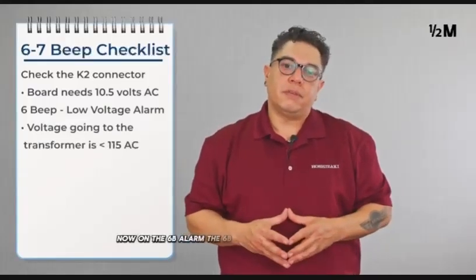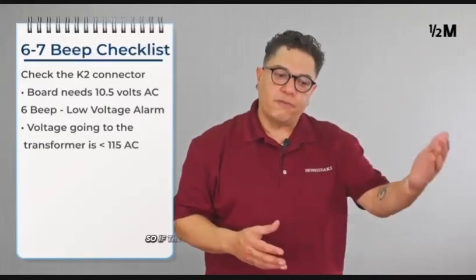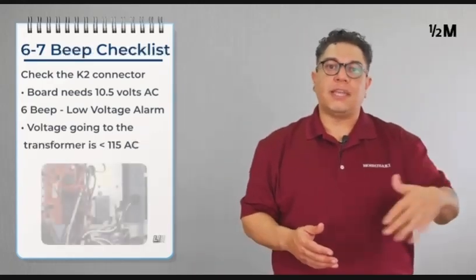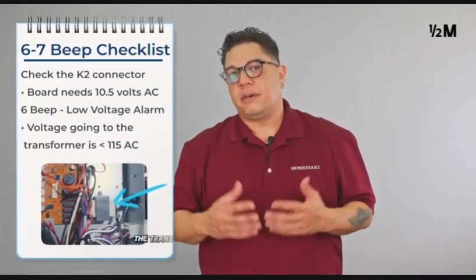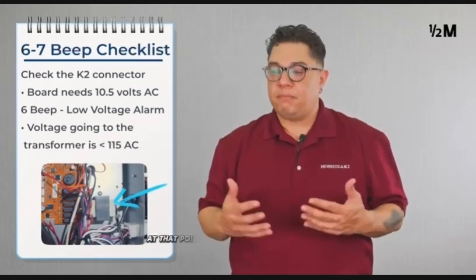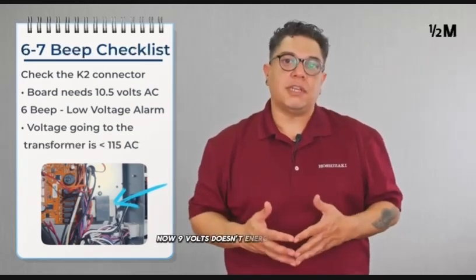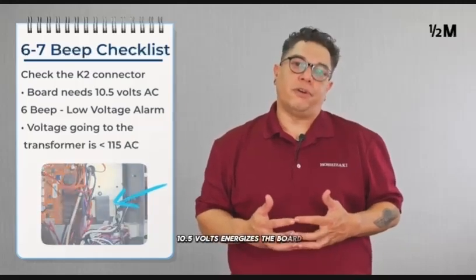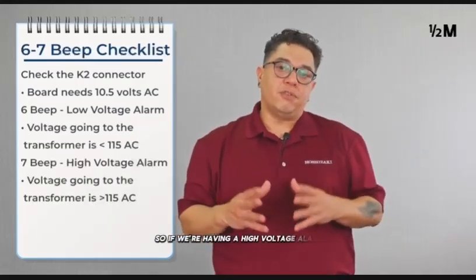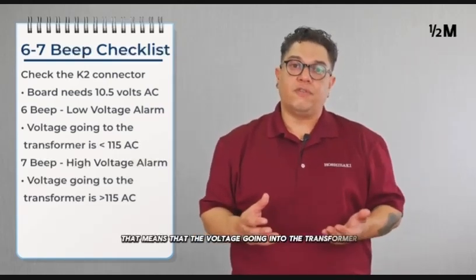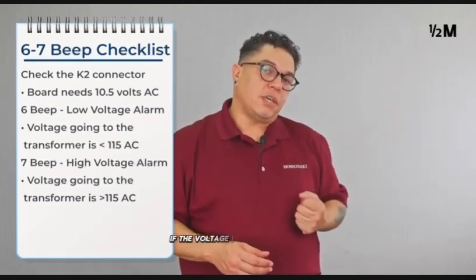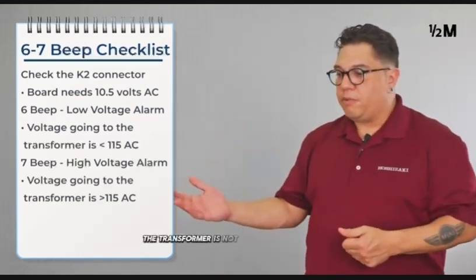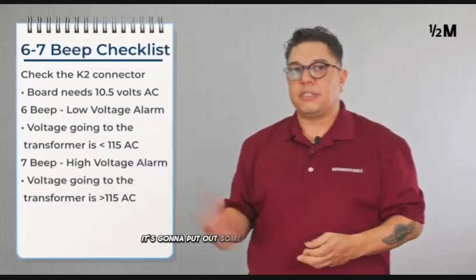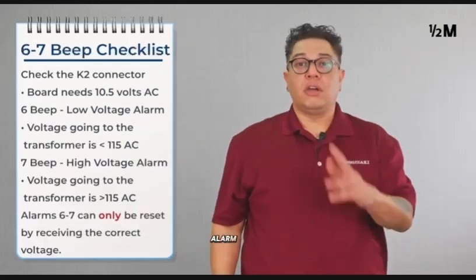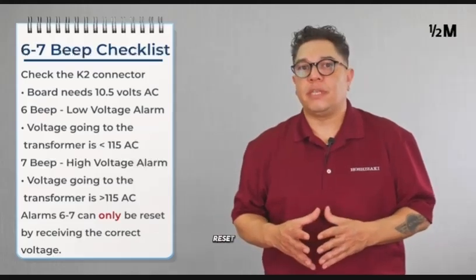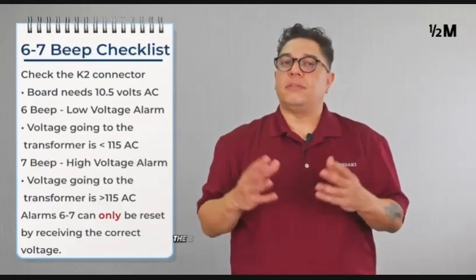Now, the 6 beep alarm is a low voltage alarm. So if the voltage is coming in lower than 115, like 90 volts, the transformer is not capable of putting out 10.5. At that point, it's going to put out like 9 volts. Now, 9 volts doesn't energize the board. 10.5 volts energizes the board. If we're having a high voltage alarm, that means that the voltage going into the transformer is higher than 115. If the voltage is coming in at 137, the transformer is not capable of putting out 10.5 volts. It's going to put out something a little bit higher, like 13.4. Alarm 6 and 7 are not capable of being reset by the alarm reset button. Once the voltage is corrected, the board automatically resets.